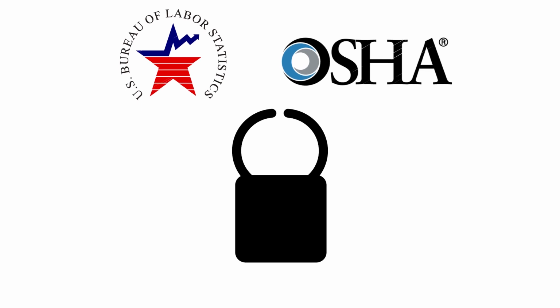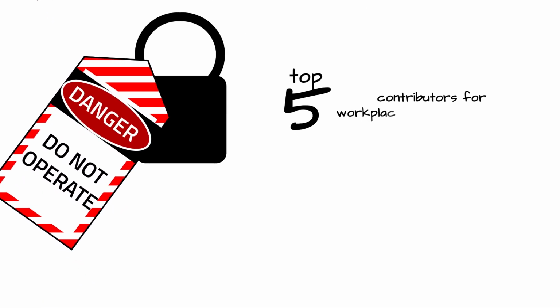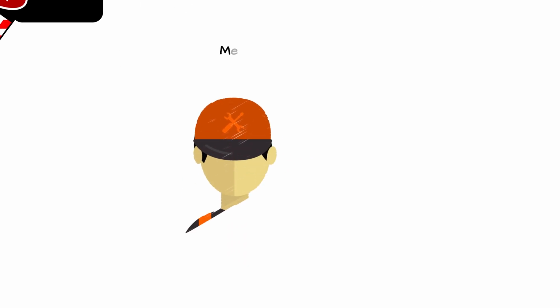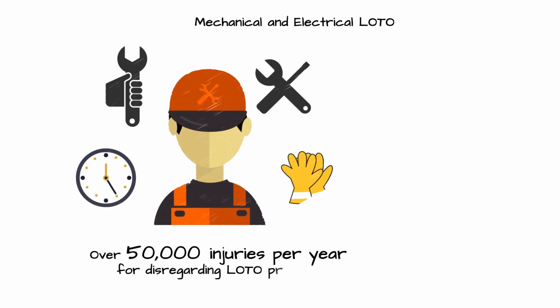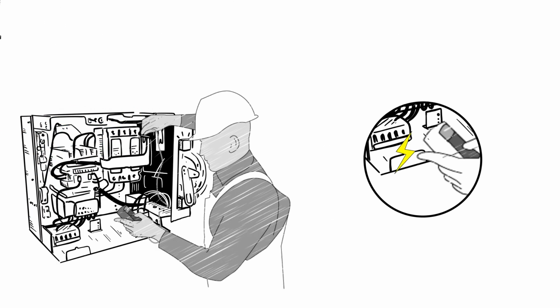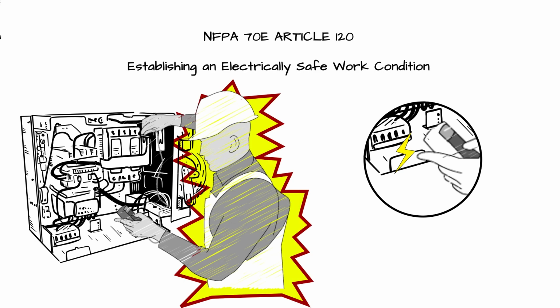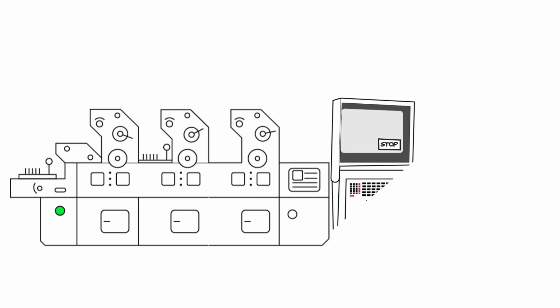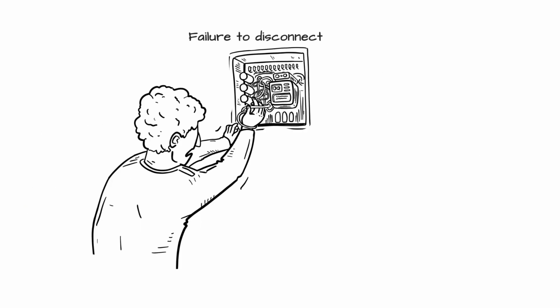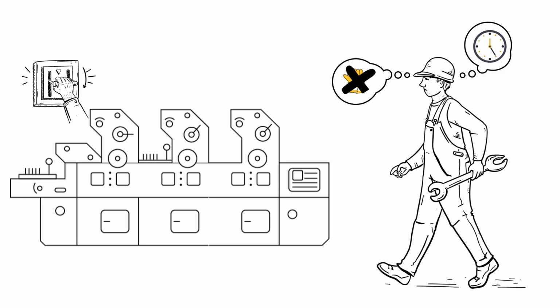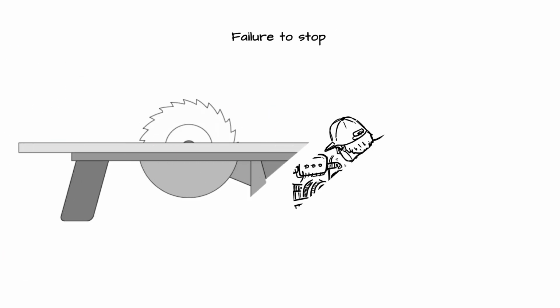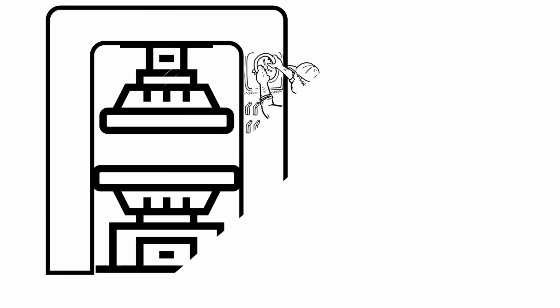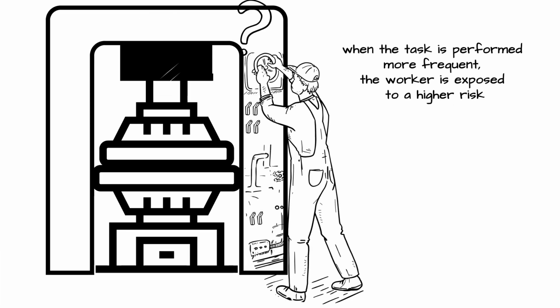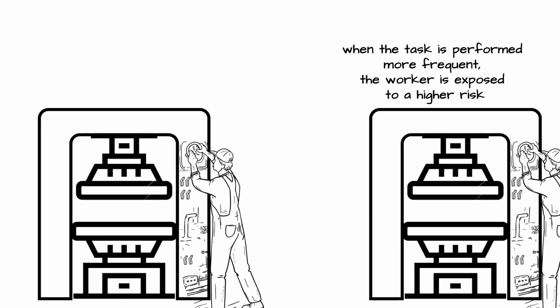Bureau of Labor Statistics and OSHA report that maintenance work involving the lockout-tagout task is one of the top 5 contributors for workplace electrical accidents. Most of these accidents occur while performing a mechanical or electrical lockout-tagout to verify the de-energized condition of the equipment, or when creating an electrically safe work condition per NFPA 70E. Studies and research also indicate that failure to stop the equipment, failure to disconnect from the power source, failure to dissipate residual or stored energy, and creating an electrically safe work condition is especially hazardous due to the task frequency, as well as being the top 3 causes for lockout-tagout preventable injuries.